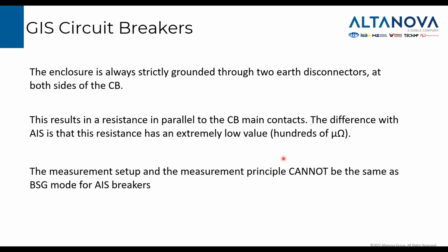The principle you need to test the timing cannot be the same that you are using for the testing of air insulated breakers. You need to introduce a different method because the resistance of the metallic enclosures in parallel to the main contact is extremely low. Most probably it is in the range of a few microohms, so it's the same value as the main contact. So during the open-close operation, if you just use the measurement of, let's say, resistance variation, you will not see any variation.